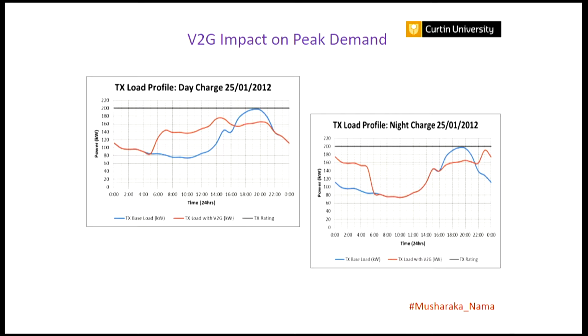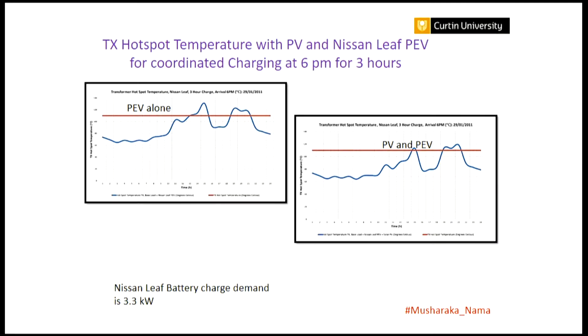I want to show you an interesting example. On the left is the hotspot temperature of a transformer, which determines the life of a transformer. If we only had the grid as we know it, no rooftop PV, no electric vehicles, we'd only have that red line, which is the standard for not exceeding hotspot temperature. You see on the left it goes above that, normally during midday.